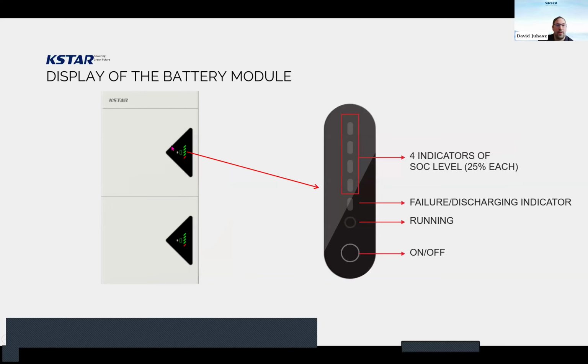There is a display on the battery packs. There are 5 LEDs, but the first 4 show the SOC level of one pack, not the system. Each of them shows 25% of the SOC. The 5th is a failure discharging indicator, and there is another indicator which shows if the equipment is running. And there is one button on each pack which is responsible for the on and off switching.